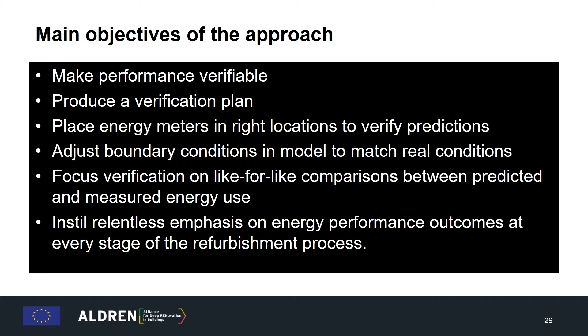The last two speakers have explained that what we're looking for here is real savings. We don't want to rely on theoretical savings, and the performance gap is well known and has to be avoided. So the key objectives of our approach have been to make performance verifiable, produce a verification plan, place energy meters in the right locations to verify predictions, and when we look at the performance gap, adjust boundary conditions in our model so we can make like-for-like comparisons between predicted and measured energy use. Lastly, and importantly, instilling this relentless emphasis on achieving your energy performance outcome, without which you're quite likely doomed to fail.